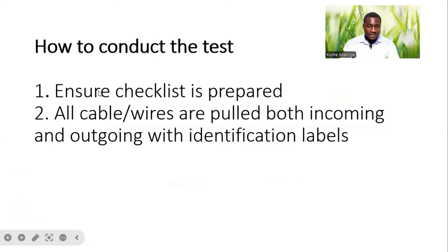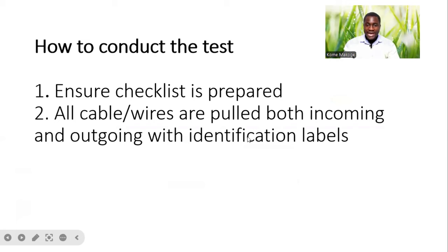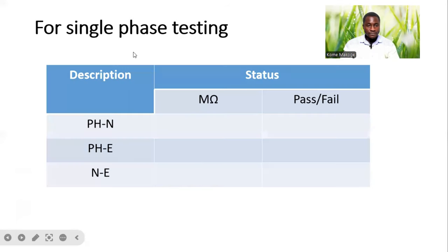How to conduct a test: we have to ensure that we get our checklist prepared. All cables or wires are pulled, both incoming and outgoing, with identification labels — this is very important. For single phase, the checklist will have descriptions: phase-neutral, phase-earth, and neutral-earth. We will measure in megaohms and then record the status, either pass or fail.